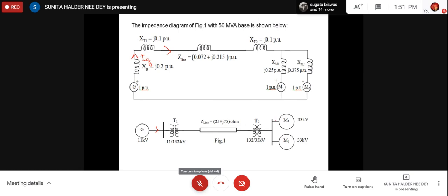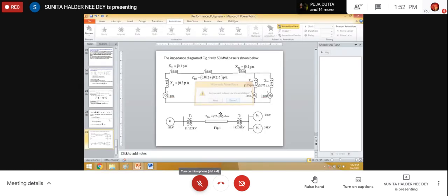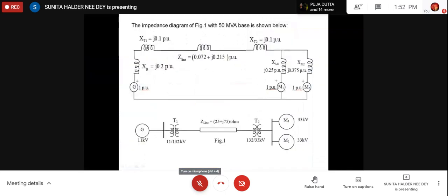Similarly, say if we want to calculate what is the motor current, right? Then we should calculate this one in per unit. So this is simple as a series parallel circuit, so you can easily calculate. You add all these 1, 2, 3, 4 reactances in series, then these two are in parallel. Then you can easily calculate the actual current to the circuit coming from the generator. Then you divide it through the shunt branch, then you can calculate any current.